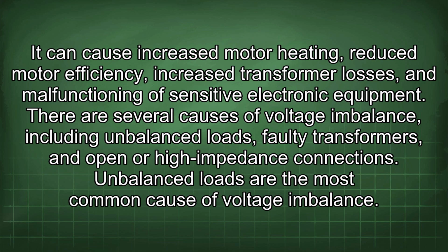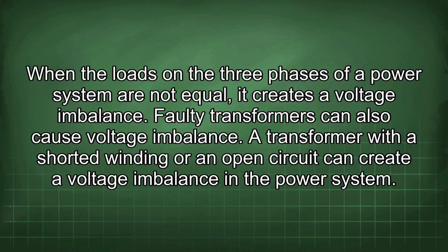There are several causes of voltage imbalance, including unbalanced loads, faulty transformers, and open or high impedance connections. Unbalanced loads are the most common cause of voltage imbalance. When the loads in the three phases of a power system are not equal, it creates a voltage imbalance. Faulty transformers can also cause voltage imbalance.